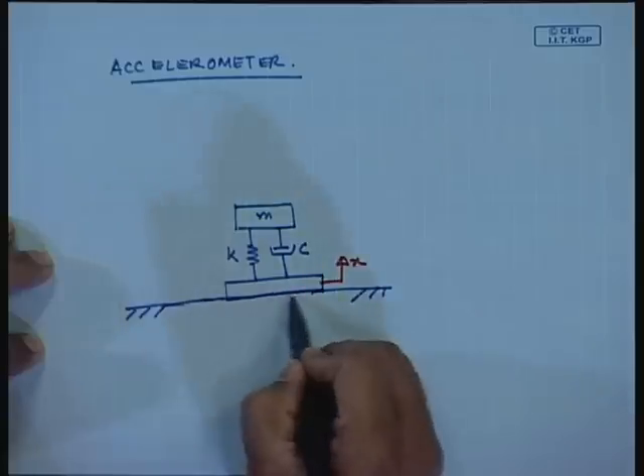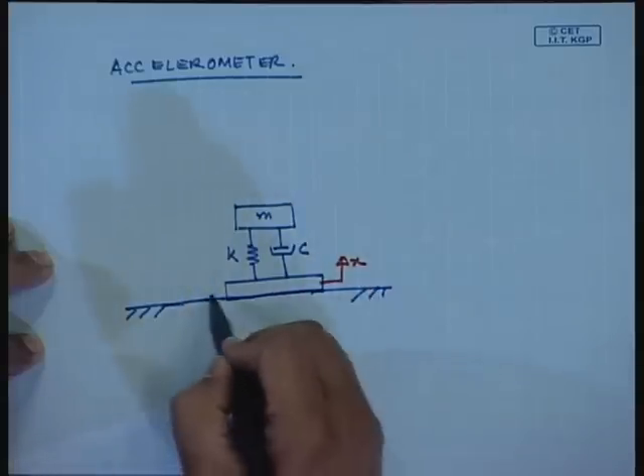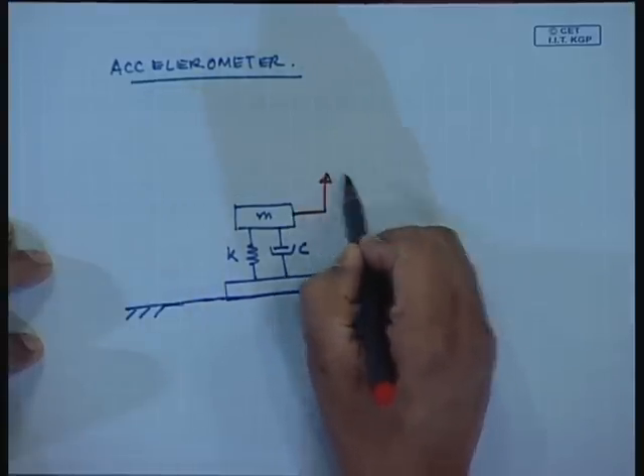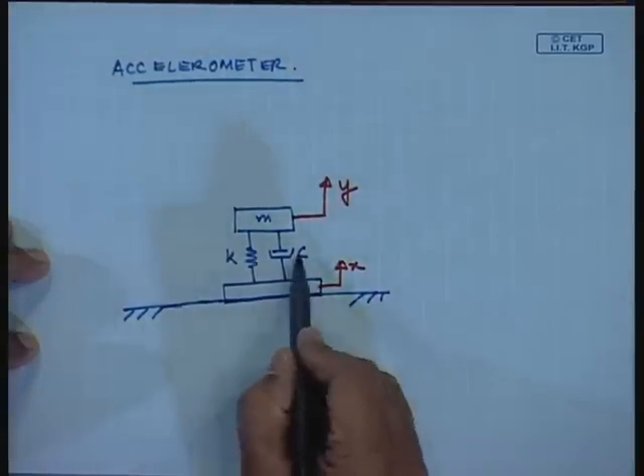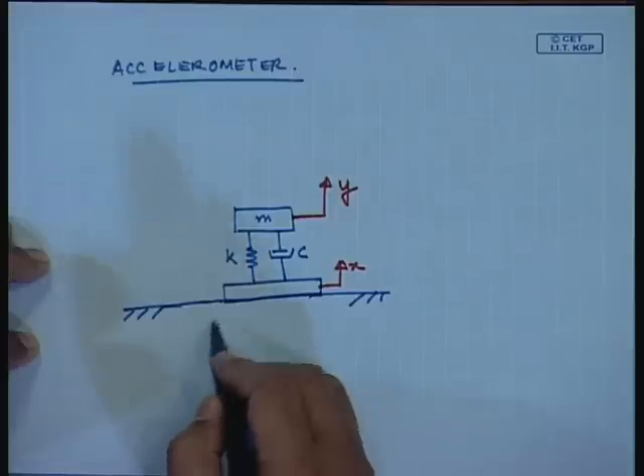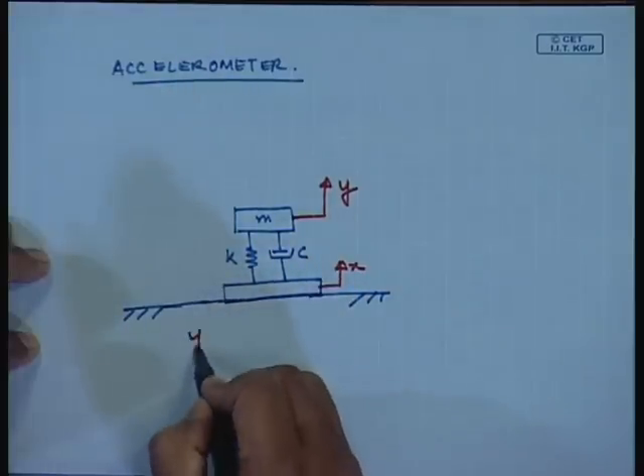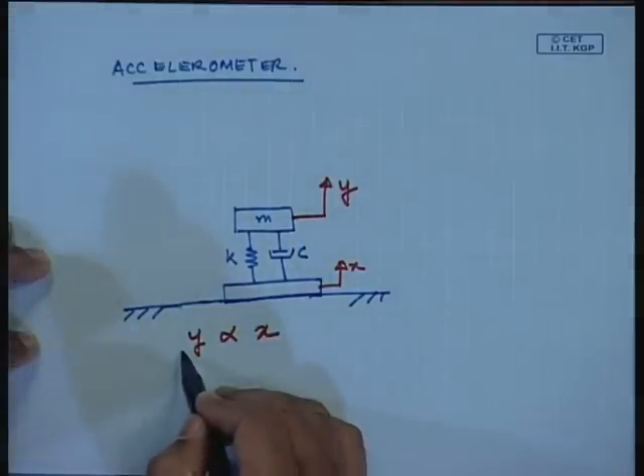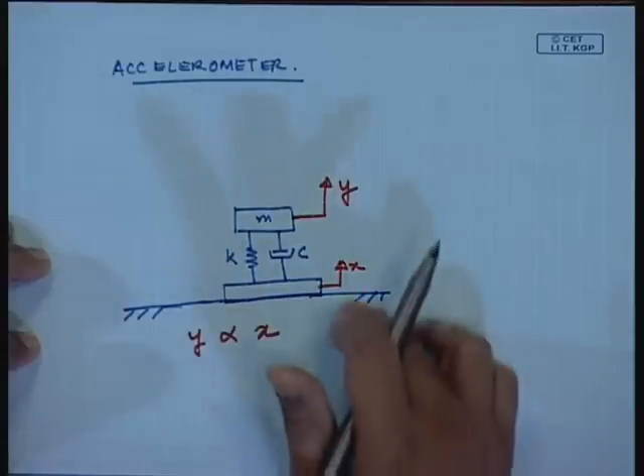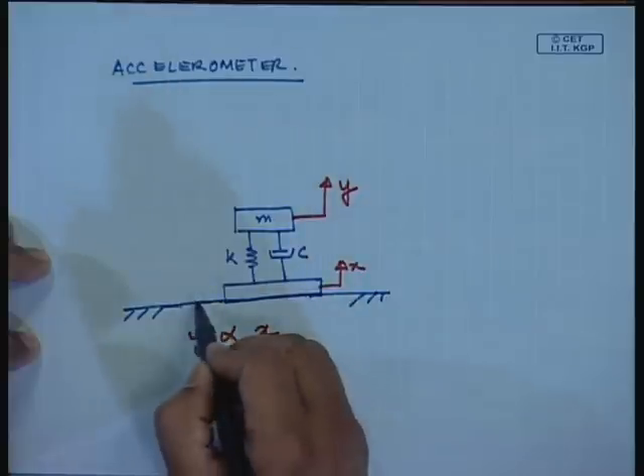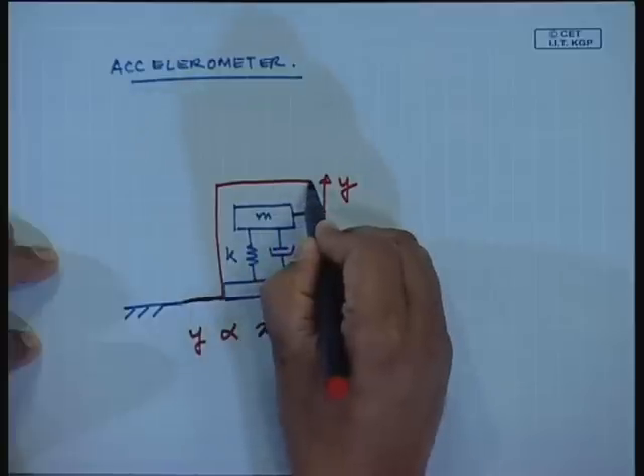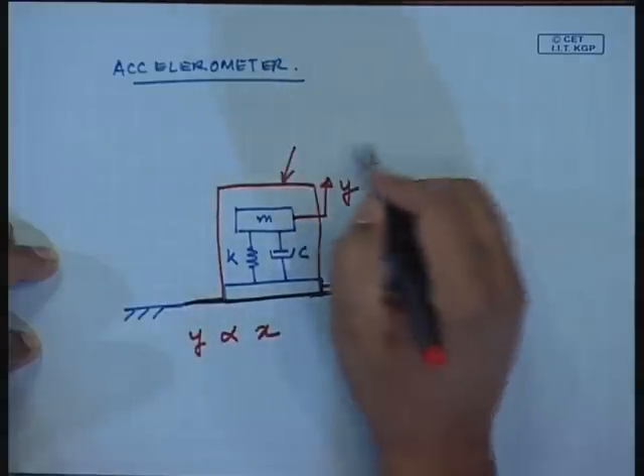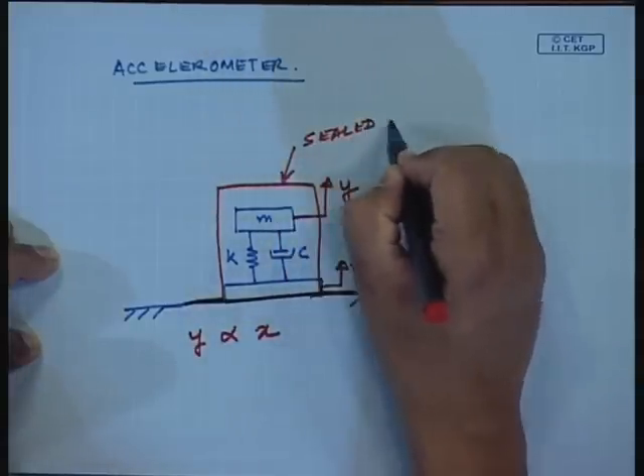Because of the motion x, this mass is going to have a motion y - dependent on the spring stiffness k and damping c. Indirectly, if I measure y, I can know what x is. This x is actually the vibration displacement, and this unit will be put in a nice housing - a sealed unit or casing.